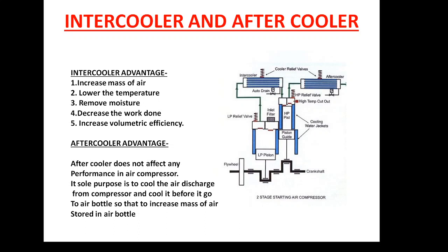Okay, but the aftercooler doesn't affect the compression cycle. Why? Because the air discharged from the aftercooler is going to the air bottle, but the air discharged from the intercooler is going to the HP stage. So intercooler efficiency affects the compression efficiency, but aftercooler efficiency does not. But if the aftercooler is getting choked, the amount of air stored in the air bottle is reduced, and that will affect it.